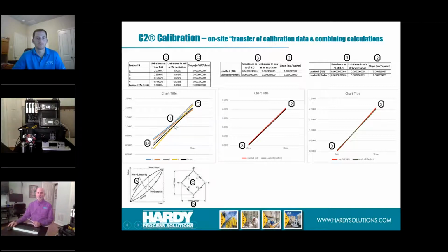Let's say, like I said, if you were in the middle of a batch and you determined that a load cell had failed, you went in and put in a new load cell of the same capacity. This is the accuracy that you can expect right here without doing a smart calibration. When you do the smart calibration, the unit then sums all of these, and it brings in the red line, the black line is still the perfect, and the red line is very close because it's in that 0.02% accuracy. This is what it looks like, just with the calibration.